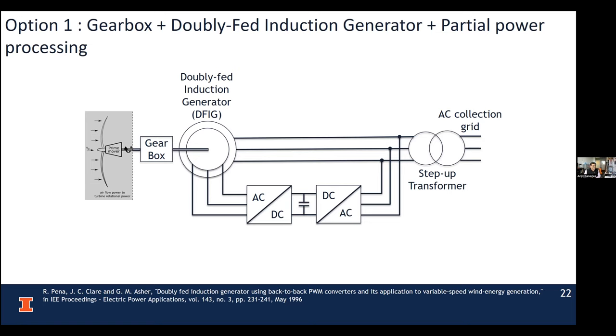But offshore, this is not so great. Why? Two primary reasons. One is the gearbox—the reliability story, gearboxes are not that reliable. Secondly, you need to convert these electrical connections from rotating frame to stationary, so you need brushes and slip rings. Particularly in a saline environment, these connections are not reliable, so you have to replace them often. That's why this architecture is not great offshore.